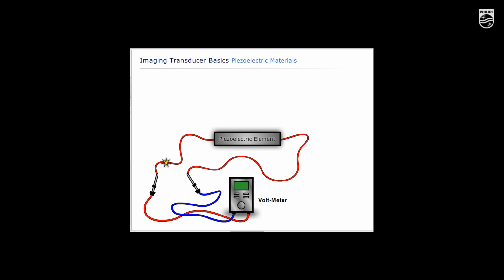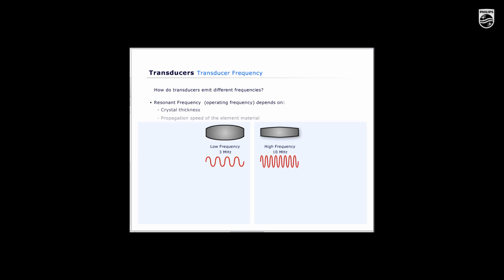The operating frequency is determined by the following: the propagation speed of the element material and the thickness of the transducer element. During the receive stage, the returning sound wave, the echo, will deform the piezoelectric element. As a result, the element will produce an electrical signal. In ultrasound applications, the driving transmit voltage is about 100 volts. The voltage produced by the element during receive is in the range of millivolts and microvolts. The operating frequency is such that the thickness corresponds to half of a wavelength in the element material. Thinner elements produce higher frequencies, and thicker elements produce lower frequencies.